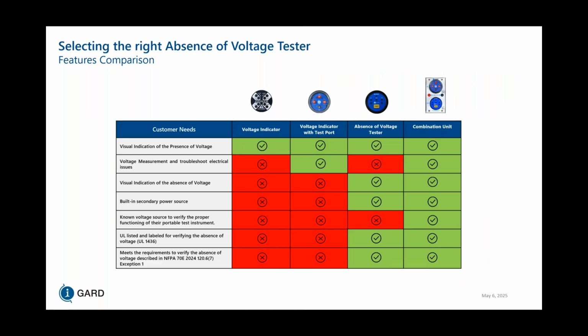So with the combination unit, you could see that we are able to satisfy a lot more than just using the absence of voltage tester. We can have voltage measurements and troubleshoot electrical equipment with the voltage test port, and also confirm absence of voltage with the absence of voltage tester. And with the known voltage source, it's just an added caveat in terms of being able to calibrate or confirm that your multimeter is properly calibrated.